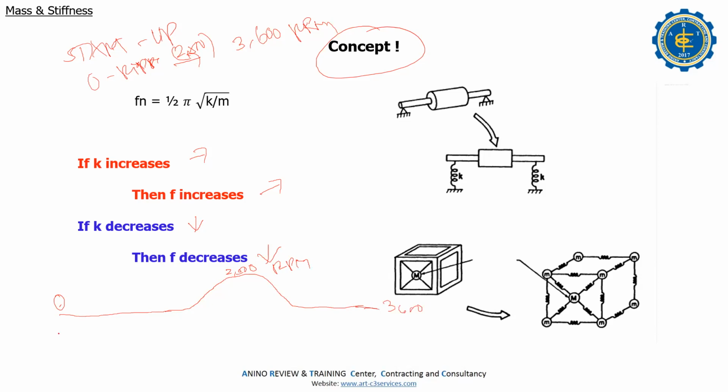Normally, that's why you shouldn't be afraid when there is a time of high vibration during an actual startup. Don't worry. You can tell them that maybe that is the critical speed of the machine.